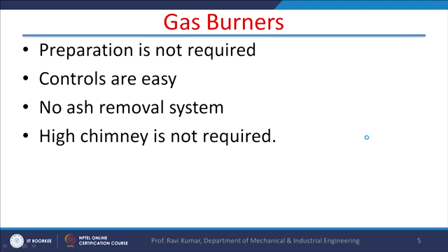Now after oil burners, there are gas burners. Their application is limited, but the benefit in the gas burner is that preparation is not required, because gas itself is a volatile fluid and is available in gaseous form. Control is easy. We can easily control the flow of the gas, so when the heat requirement is less, we can turn the control valve and control the heat release rate of the fuel. An ash removal system is also not required, because in gaseous fuel there is no ash, and ash removal is a big job in a thermal power plant. Chimneys are also not required. So these are the benefits of gas burners.